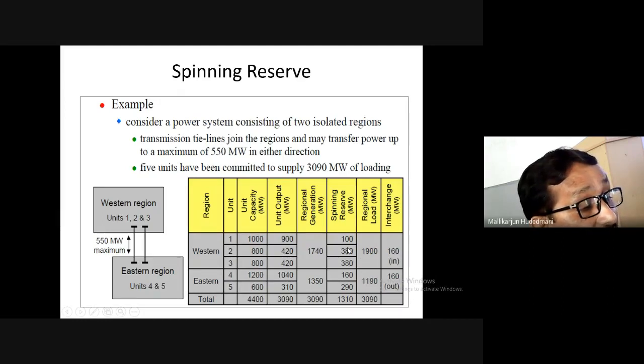Suppose the load in area 1, western, still increases to 2000 megawatt without changing the set point. What can I do? I can change the set point in area 2. I can pull or pump higher power here. In this regard, I want to narrate. Let us say column-wise accumulation.